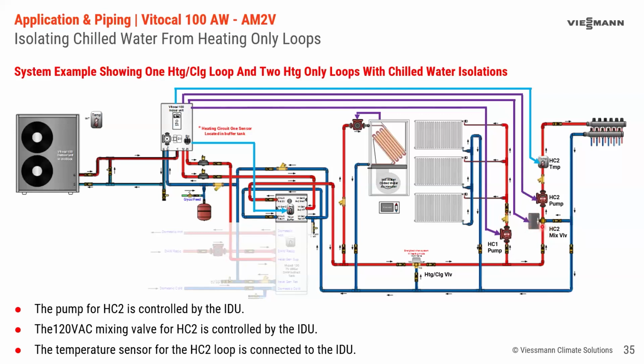This valve here will then maintain the mixed temperature by bypassing some water here. So this is circuit 1 now and circuit 2, both enabled, but circuit 2 has 2 loops, one with the pump running from the indoor unit and one running with the pump from the air handler. And again, none of this has a thermostat or a dry contact or anything that comes back to the indoor unit. The indoor unit is maintaining the buffer tank, and these systems are drawing off of the buffer tank.